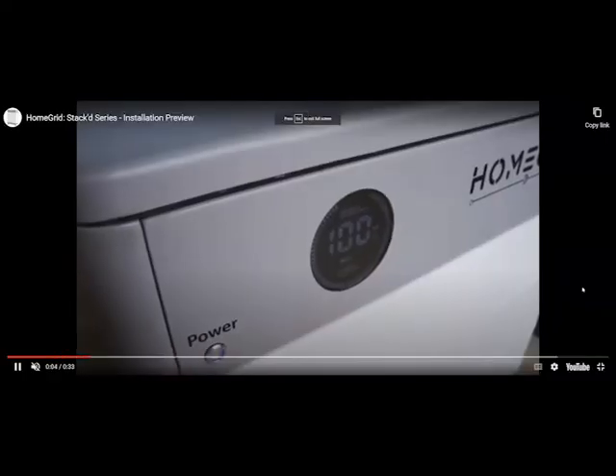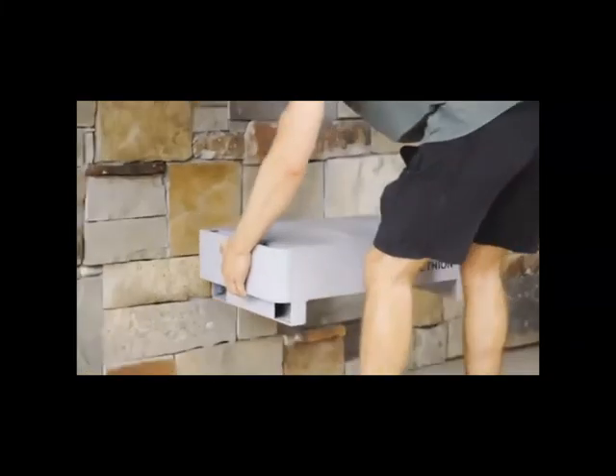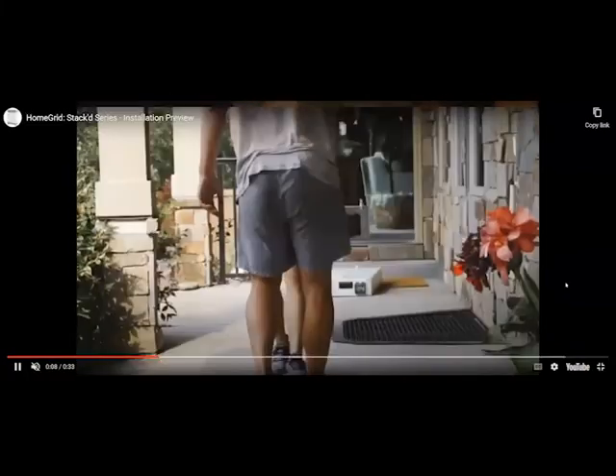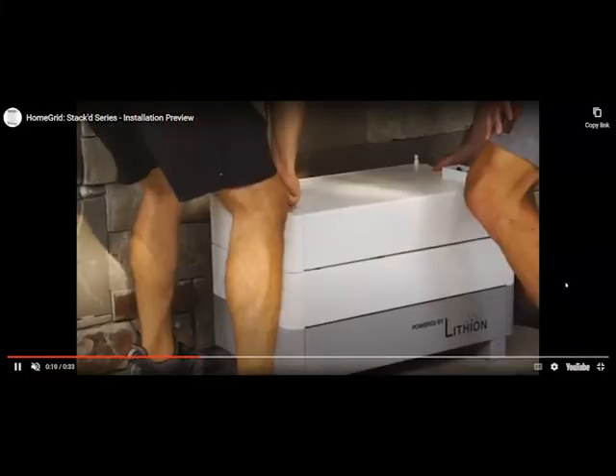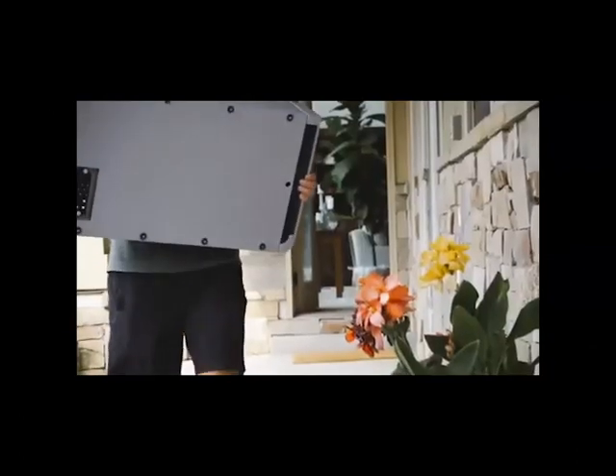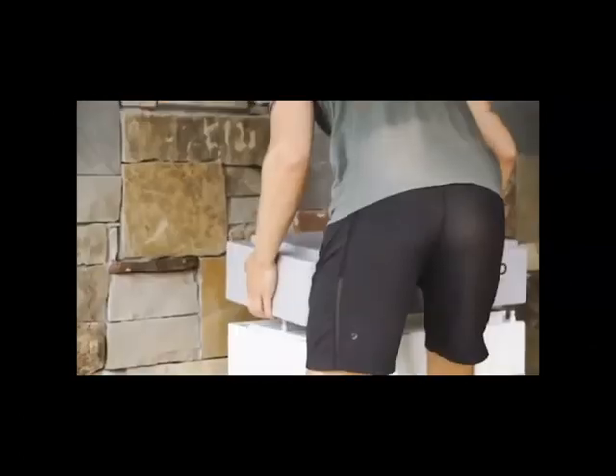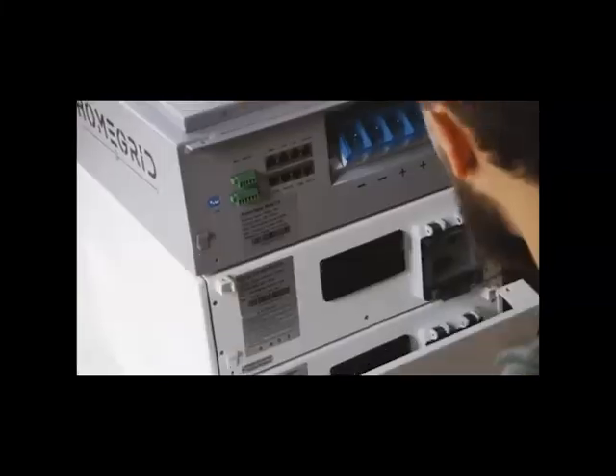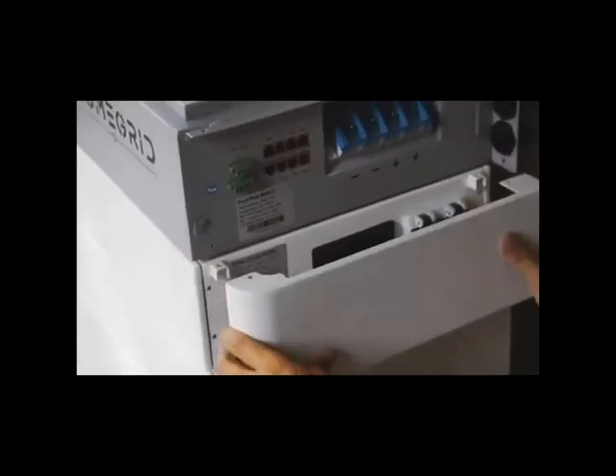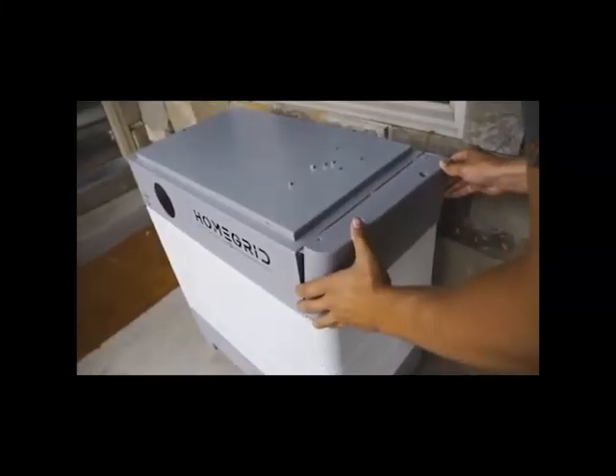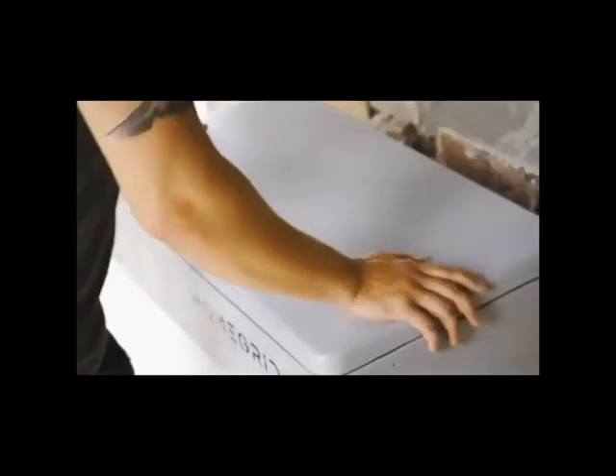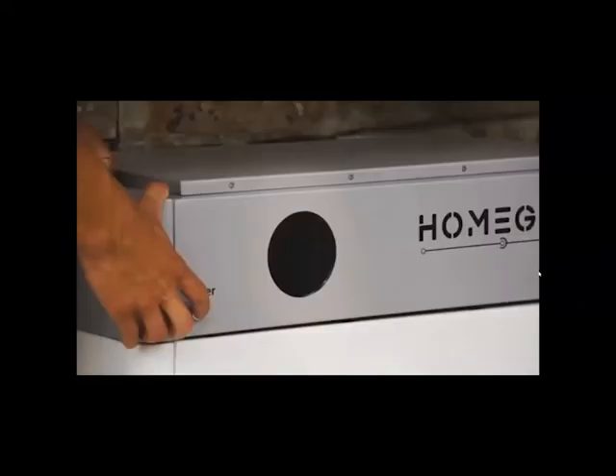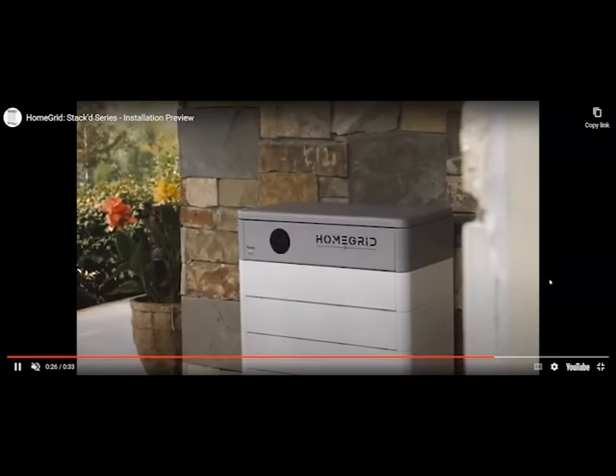Each of our white modules is 4.8 kilowatt hours. They stack just like Legos, so there's no wiring between the modules - just a male and female connector. We can stack anywhere from 2 to 8 of those white modules in a single stack, giving you a massive capacity range of 9.6 to 38.4 kilowatt hours.